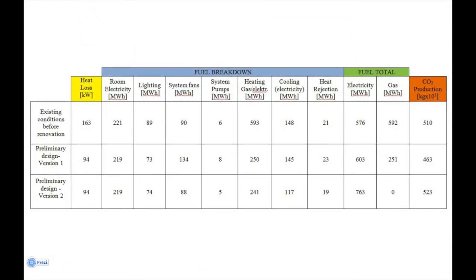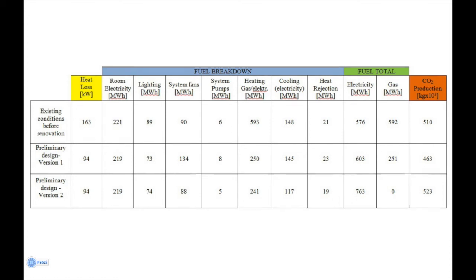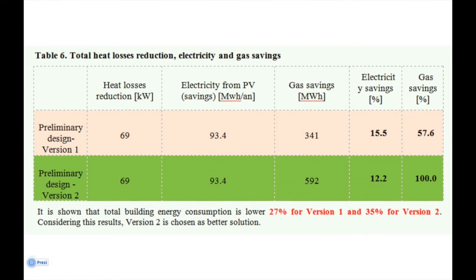According to all simulation results, energy consumption for building before renovation is compared with building after preliminary design renovation. Results are shown in this table. Heat losses, energy consumption, fuel total needs and CO2 production for version 1 and 2 in comparison with building condition before renovation. Regarding those results, energy and fuel total savings are shown in the comparison with existing building before renovation. Total heat losses reduction, electricity and gas savings. It is shown that total building energy consumption is lower 27% for version 1 and 35% for version 2. Considering these results, version 2 is chosen as better solution.